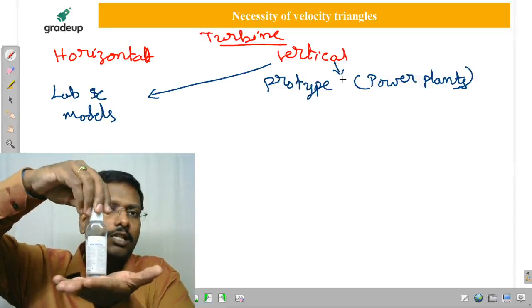Why are we going to use this? Footstep bearing will be used to bear the heavy loads. So here we have to use journal bearings. That is why whenever it is a model or in the labs, we use horizontal turbines. Even in some labs, vertical turbines are present, sir. There also they are placed with the help of journal bearings. But once it is a prototype in power plants, you won't observe a horizontal turbine; in all the cases it is always a vertical turbine. Then automatically a footstep bearing will be used, which can bear more load. That's why vertical shaft turbines are used in power plants, whereas in labs we use horizontal.